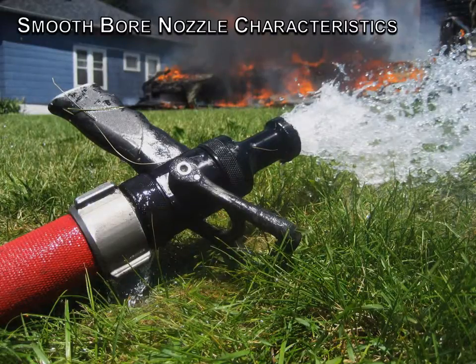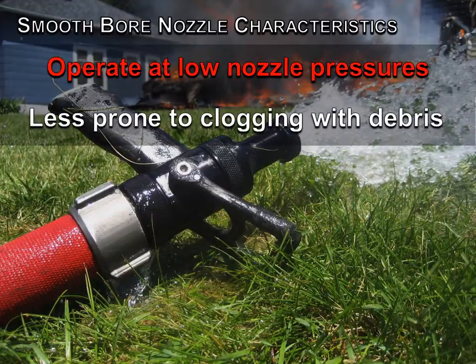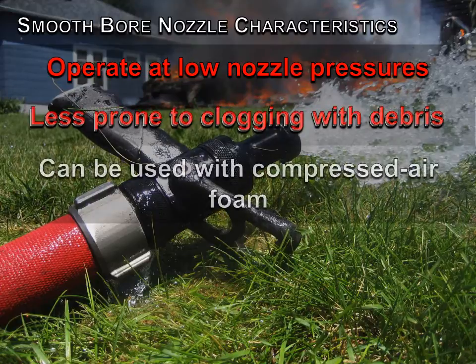The characteristics: they operate at low nozzle pressure, normally 50 psi, and are less prone to clogging with debris. You don't have anything in there. You can look down in there, see the ball valve, so there's nothing to obstruct if you get something in your line. They can be used with compressed air foam.